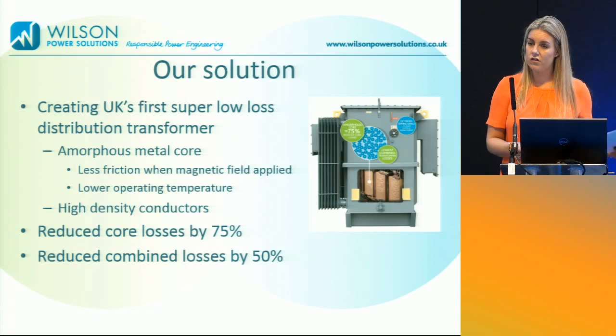So combining the amorphous metal cores with low current density conductors, the unit's core losses are reduced by up to 75%. And as a rough guide, overall it cuts transformer losses in half, making the E2 the most energy efficient distribution transformer in the UK.